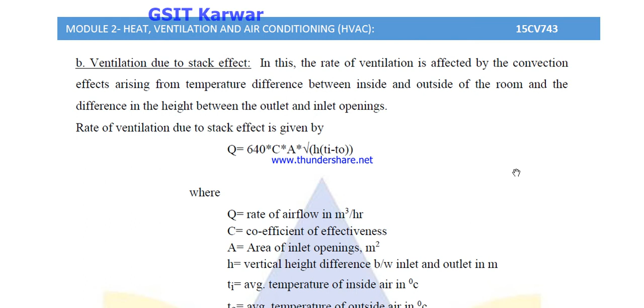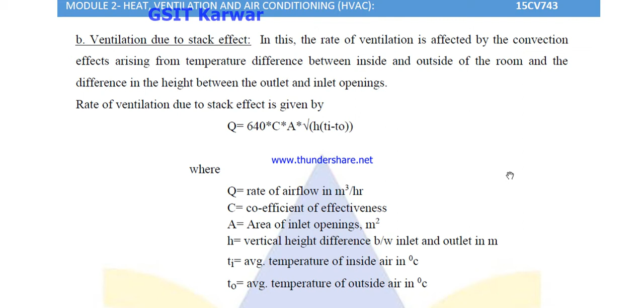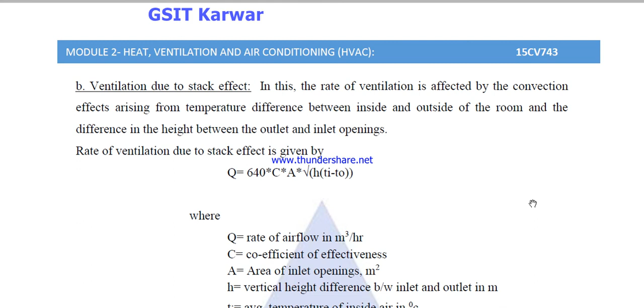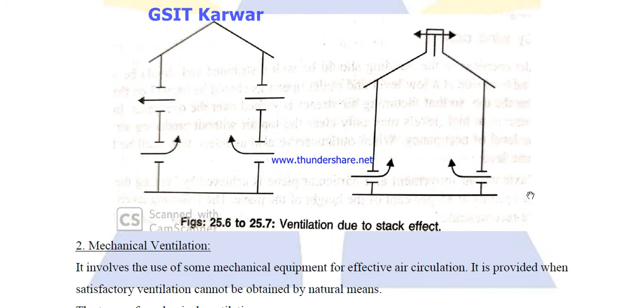And the next is the ventilation due to stack effect. In this, the rate of ventilation is affected by the convection effects arising from temperature difference between inside and outside of the room, and the difference in the height between the outlet and inlet openings. Rate of ventilation due to stack effect is given by this formula. The following formula you can observe is a very simple formula. You can directly take it if you want to calculate the stack effect. And here the elevation is given. You can observe ventilation due to stack effect, how it acts in the building.